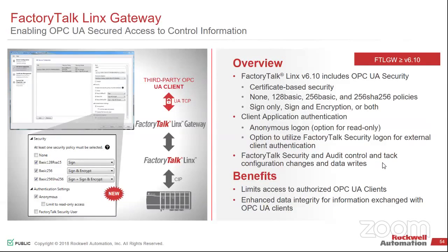So when we tie that in, the newer version, version 6, made it so we can do OPC UA natively. So from an HMI point of view, if we're looking at FactoryTalk View SE, I can now bring in OPC UA data directly into the HMI as a function. The FactoryTalk Linx Gateway now gives me the ability to be an OPC UA server and send data out somewhere else. So I can now, at the bottom end, tie into all my controllers, keep it CIP, keep it EtherNet/IP to the HMI, and now feed that information out via OPC UA to somebody else.